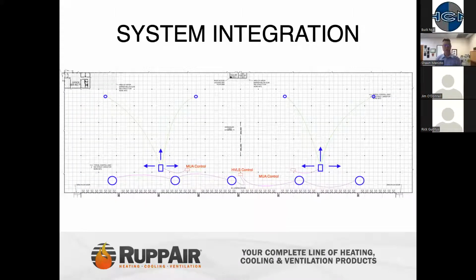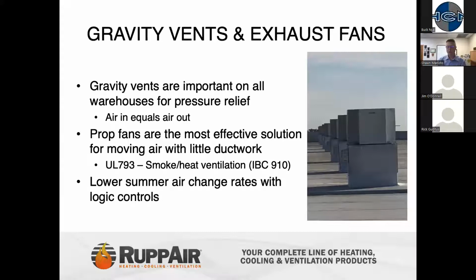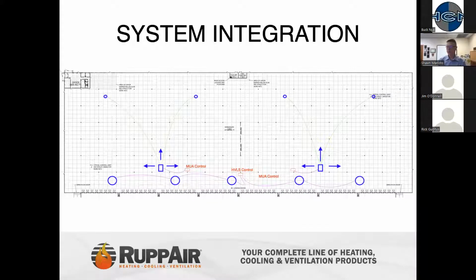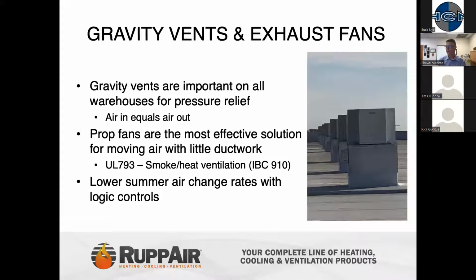So that's one reason why system integration is so important. This illustration shows about a 300,000 square foot warehouse integrating all the products that should be used in a system in a warehouse application. Now I'll go through these one by one. So most importantly, if nothing else, beyond just having those heaters in the building, is having gravity vents in place. Again, air in is air out.